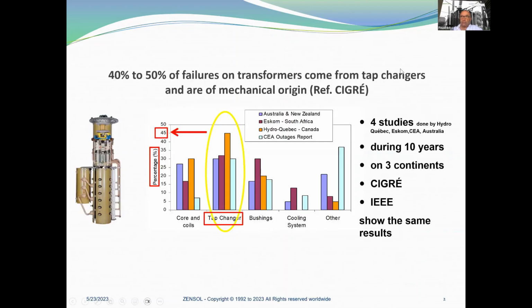So 40 to 50% of the failures on transformers come from tap changers and are of mechanical origin. Four studies done by Hydro-Quebec, ESCOM, CEA, Australia during 10 years on 3 continents, confirmed by Cigre and IEEE, show the same results. Here you have a graph where you can see that 45% of the failures come from the tap changers.